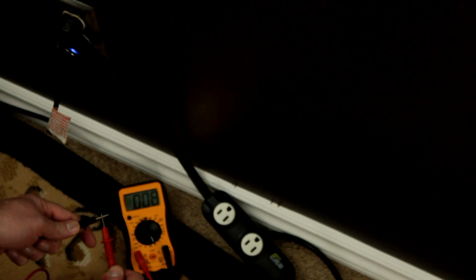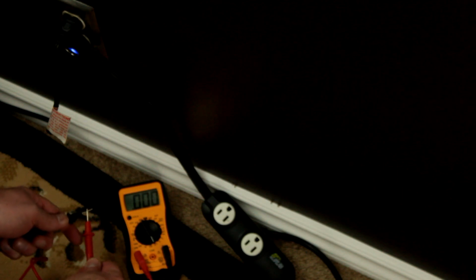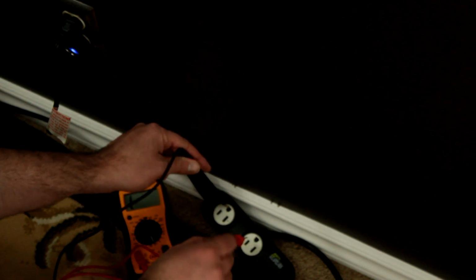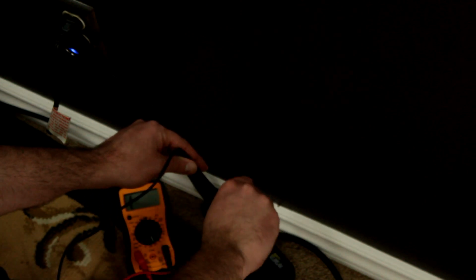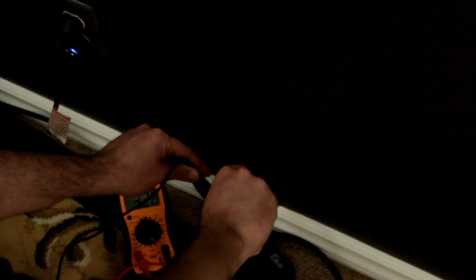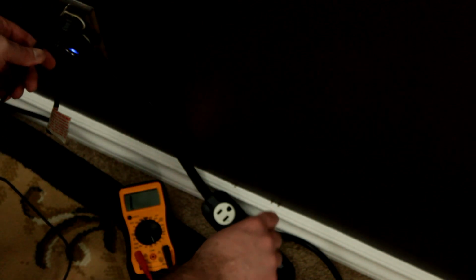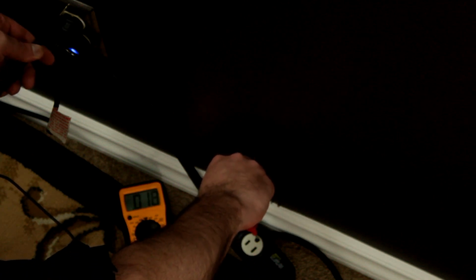The multimeter can also be used in a mode that is called continuity or tone mode. And in continuity mode, whenever the line connects, you get the high-pitched tone that you're hearing. This can be good for checking the fact that you actually have ground everywhere you expect. So we're going to plug into the ground plug on the power strip, and we get a clear tone. Now, because I run these metal faceplates that are tied in with a grounding screw, my faceplate is also grounded. So you get continuity across the ground here and there.